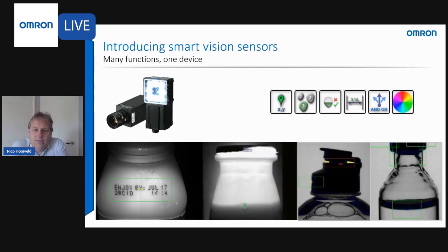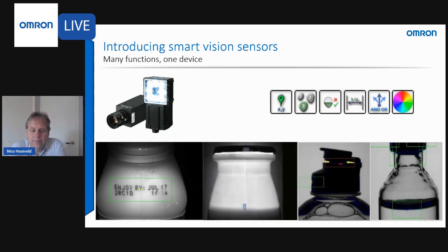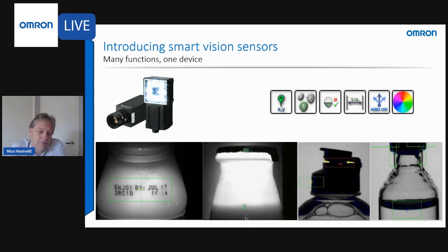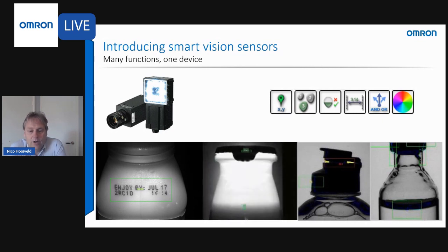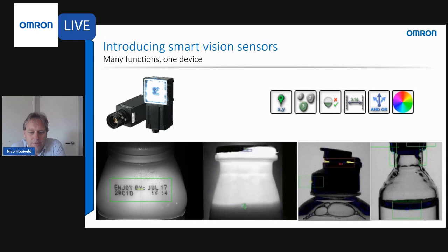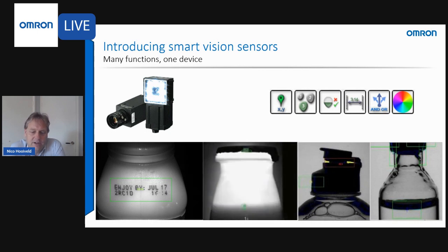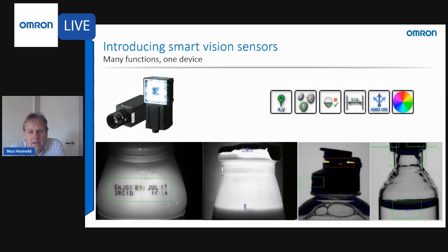The fact that vision sensors use an internal inspection program makes them very flexible, because you can change this program when the requirements or the product changes. Like traditional sensors, vision sensors can output a pass-fail signal, but in addition the inspection software can output a range of measurement data too. Vision sensors quite often come with network interfaces such as EtherNet/IP or Profinet I/O, making them very easy to integrate into PLC control systems. The latest generation products require no programming at all — instead, they are configured with a graphical user interface using drag and drop tools.